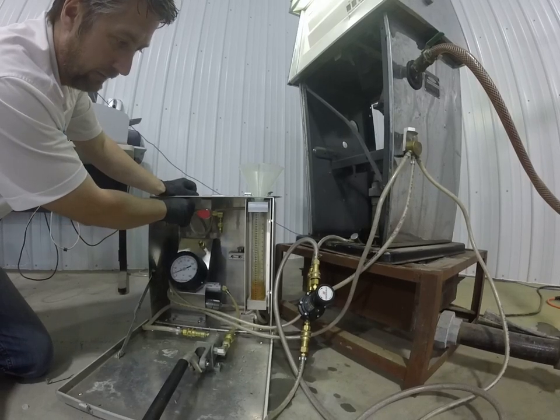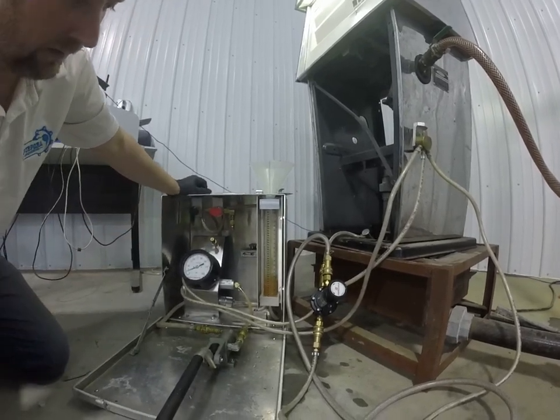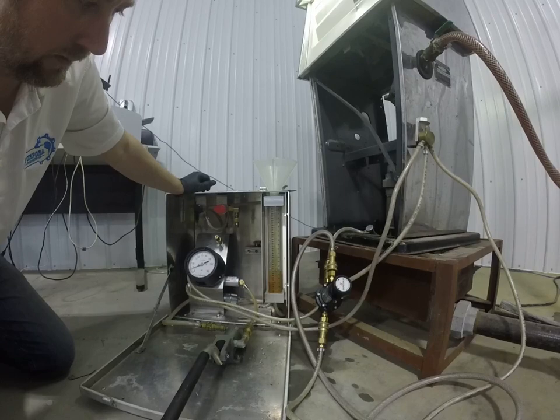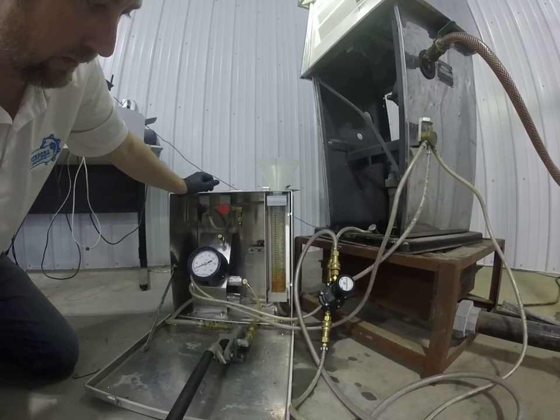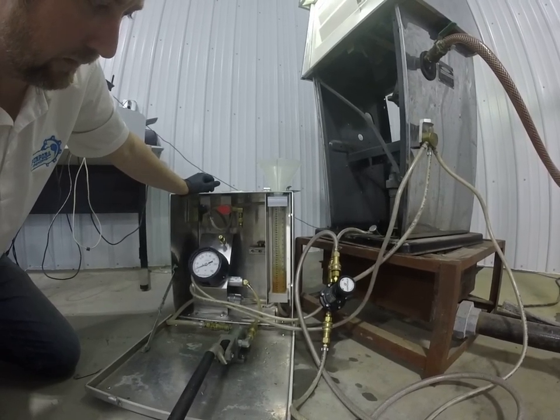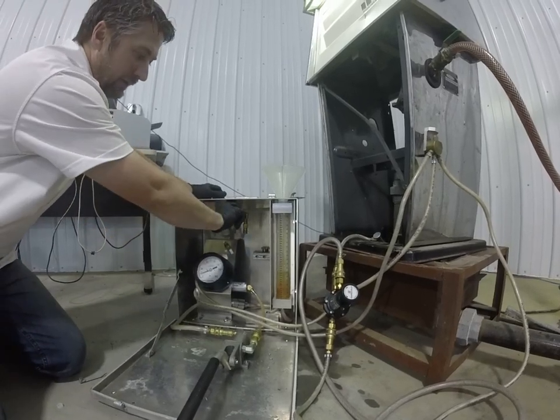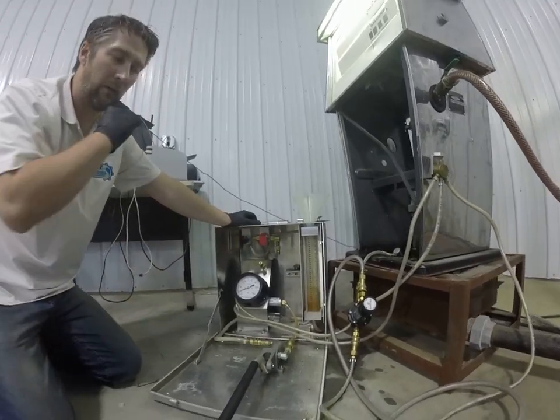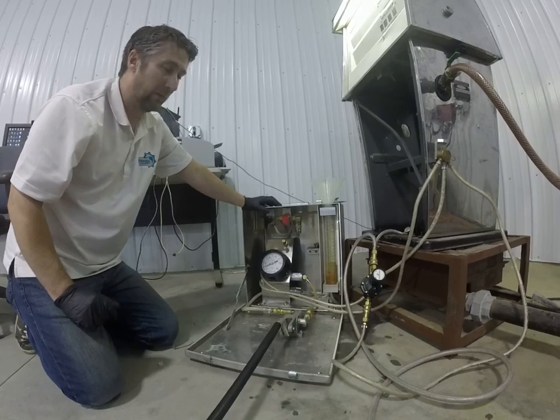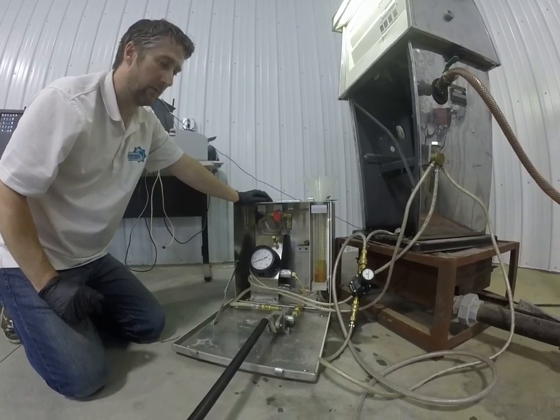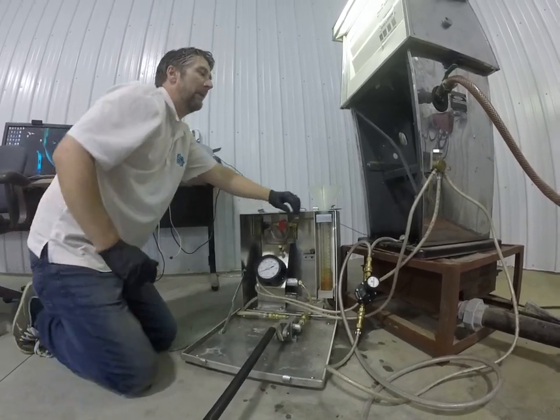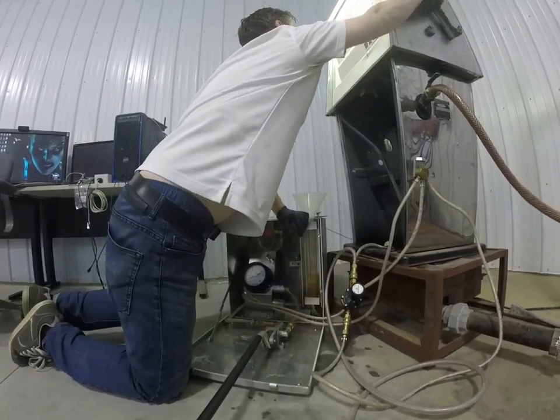That's a bit high, so we can reduce that down. 1, 2, 3, 4, 5. That's about right. So now we turn the red valve to the 12 o'clock position, shutting off the leak. You must not touch the black valve at this point. So once we have that, we can switch off the dispenser.